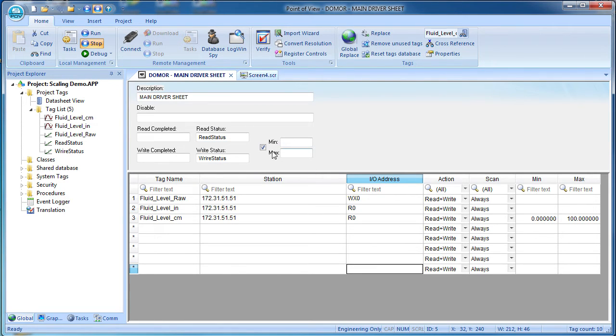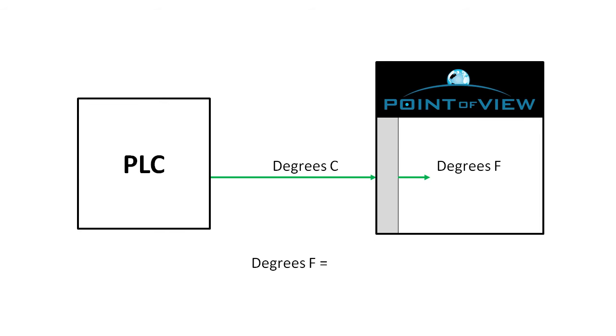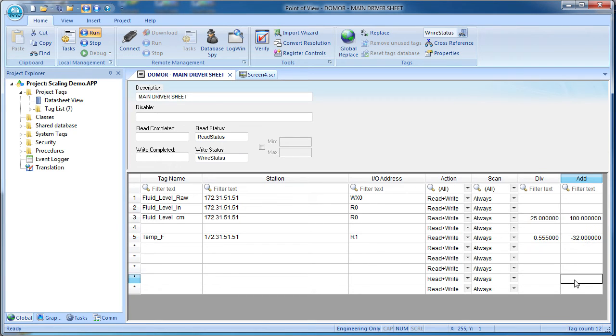it's important to understand that whichever method you choose to convert data coming into Point of View, it's automatically converted back when it heads back out of Point of View. For example, suppose the PLC is sending Point of View a temperature in degrees C, but we want it in degrees F. That equation is degrees F is degrees C times 1.8 plus a minus 32 or degrees C divided by 0.55 plus a minus 32. Same thing. So we put 0.55 here and a minus 32 here and Point of View does the conversion for us in both directions.